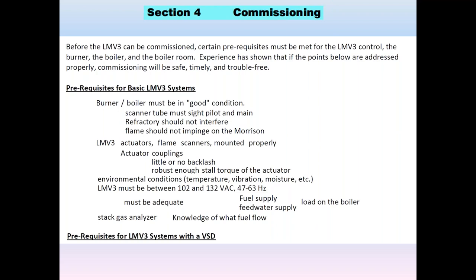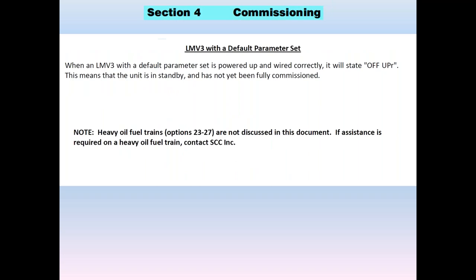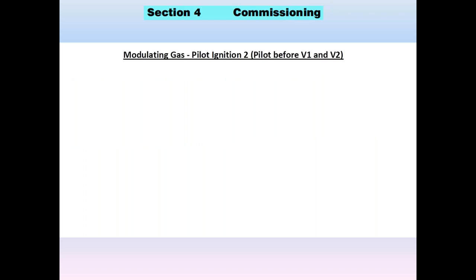There are additional prerequisites for the LMV3 VSD or PWM detailed in the commissioning sections. When an LMV3 is powered up and wired correctly, it will display 'off unprogrammed,' meaning the unit is in standby and has not yet been fully commissioned. There are various stages of commissioning, and until completely commissioned, you will always see 'off unprogrammed.' This manual does not deal with heavy oil fuel trains — options 23 to 27 — which are rarely used in the United States. Contact SCC for assistance with heavy oil trains.